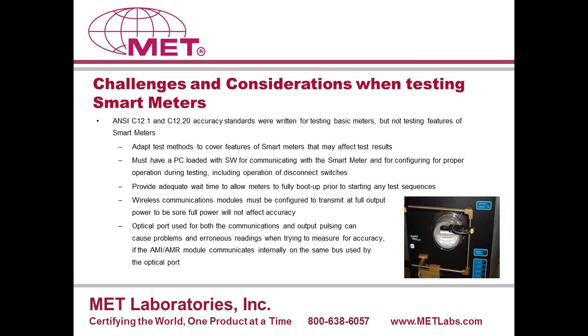But also we want to make sure that any effects of having a wireless module, for example, in the meter itself is not going to affect the results of the test. We want to make sure that we're adequately operating that wireless meter to the fullest extent, or to a reasonable extent anyway, to prove out that no problems are going to be seen in the field, at least from a test lab perspective, and being able to simulate a real-world environment from a test lab perspective. We're going to try to make assurances that there's nothing that's going to affect the accuracy of that product.